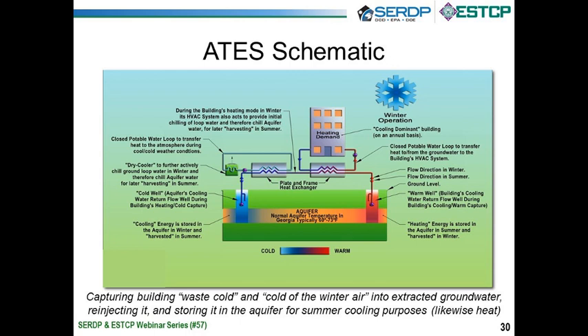But ATES is neat because it allows you to do things very efficiently by taking liquid water in and out of the ground. I'd like to start with this illustration, and let's say we've been running the air conditioning all summer. We've dumped heat down into the so-called warm well. The orange band here represents the aquifer. We've heated the water up above the normal aquifer temperature, maybe by 10 degrees or so, not a huge amount. We pass the warm water out through a plate and frame heat exchanger. We don't want to run the groundwater through the building, because groundwater can have minerals and all kinds of issues. In this particular case, we're also excited to be using anoxic water. There's no oxygen in the water, and we want to keep it that way. We don't want dissolved gases to come out. So we essentially have a somewhat closed loop on the ground loop side, and we just run it through an off-the-shelf plate and frame heat exchanger.